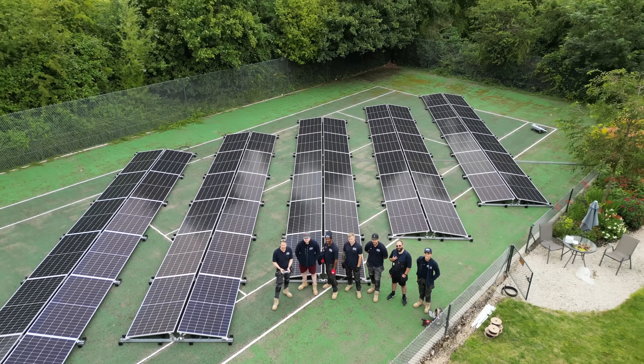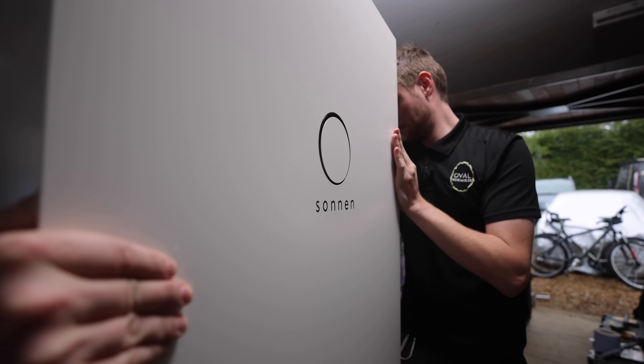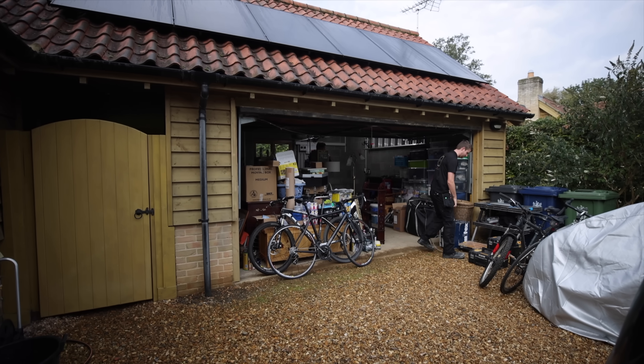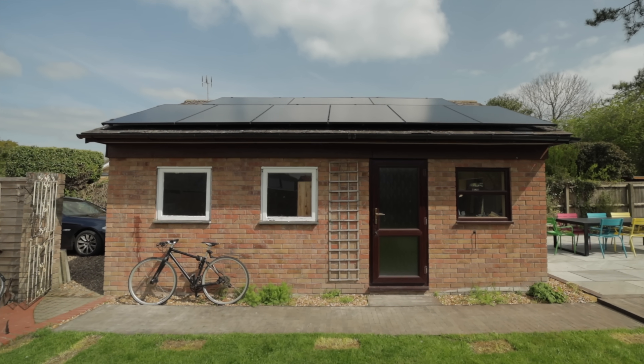Here at Artisan we like to do things properly and we always work with care and attention. Rewind back to three years ago when we did our first battery storage install with Oval Renewables — where did we fit the battery? It was in a garage, away from the main house. I've always felt that when installing a battery you want to be ideally as far away from habitable spaces as possible. We have never installed a battery in a loft. But there was no specific legislation or guidelines saying you can't do it, and of course it's often way easier to stick the batteries in the loft if the inverter is already up there. So thousands and thousands of installations have been done with batteries fitted in lofts.